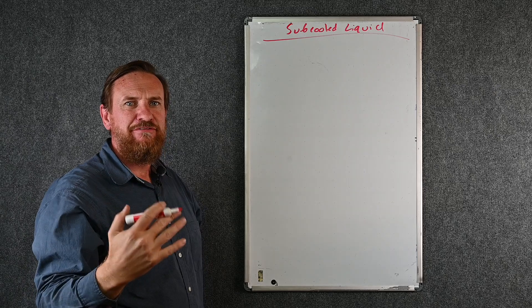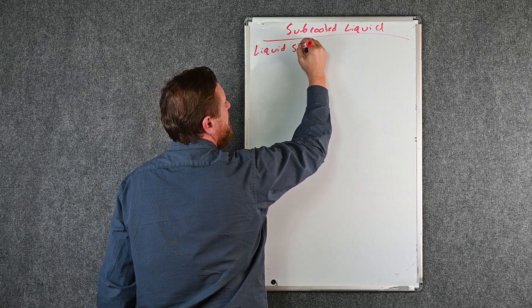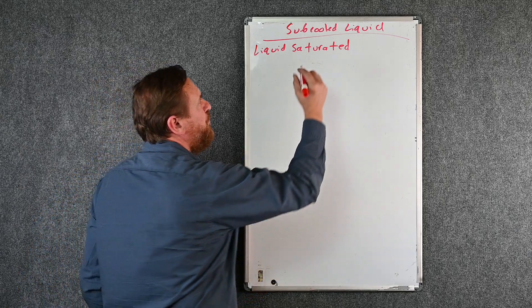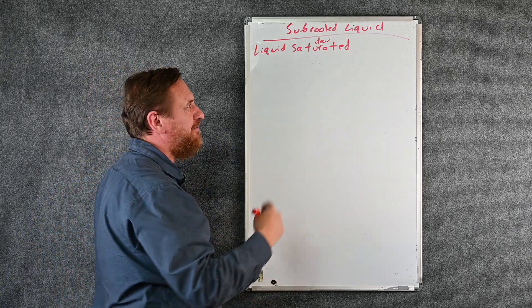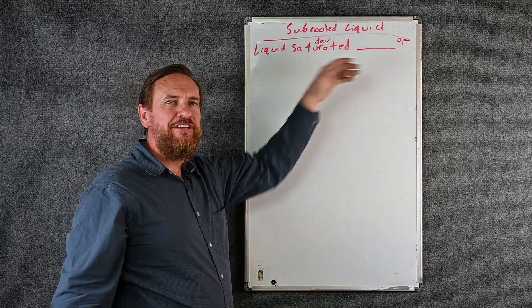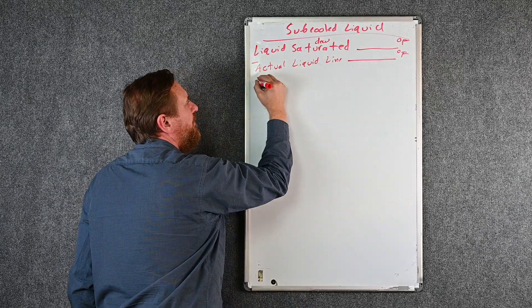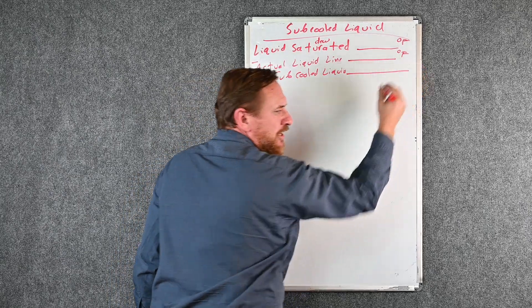Write at the top: Sub Cooled Liquid — write it in red. Red for sub cooling. Now let's put the formula. We're going to have: Liquid Saturated Temperature — and also add the word 'dew' here, we'll need it soon. We want the dew saturated temperature. So it's: Liquid Saturated Temperature (blank degrees Fahrenheit) minus our Actual Liquid Line Temperature (blank degrees Fahrenheit) equals Sub Cooled Liquid.